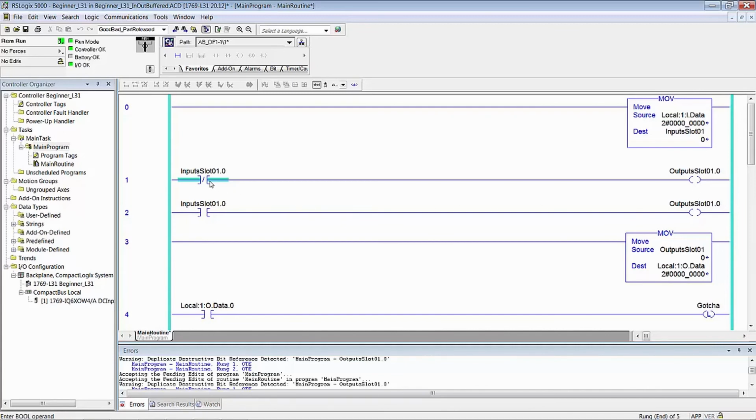You see this bit going on in memory because it is going on. Remember, I told you this rung is true, turns that bit on. This rung is false, turns that bit off. So guess what? This graphical user interface, RSLogix 5000, is looking at the data table. It's not looking at the code. This ladder logic you see here, that's a figment of our imagination. It only exists to present a relationship of the data with the machine level language that's in there executing the code right now. We are actually looking directly at that bit in memory.